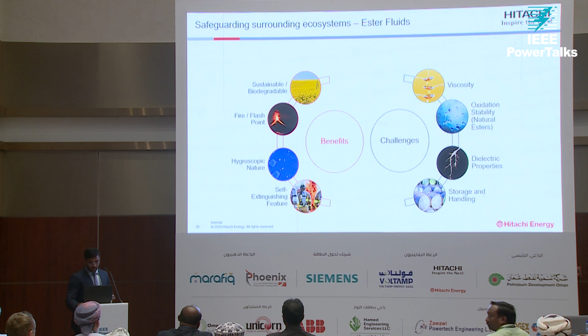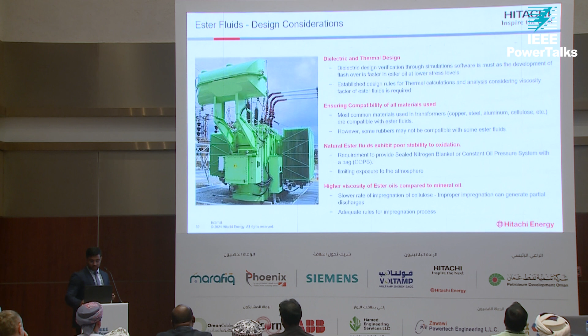Again, with utilization of ester fluids, which are biodegradable and environment friendly, some special design criteria are required, such as dielectric and thermal designs and ensuring compatibility of all materials used. Most materials used in transformers, like copper, steel, and aluminum, are compatible with ester fluids. However, some rubbers may not be compatible with these ester fluids. Natural ester fluids also exhibit poorer oxidation stability and higher viscosity compared to mineral oils. These are the main design criteria to consider when using ester fluids in transformers.